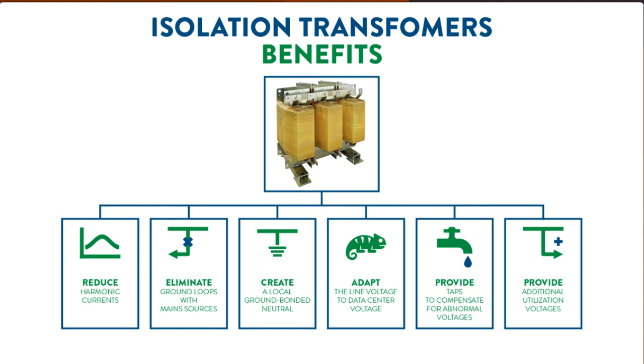But the most important one is to create a local ground-bonded neutral. This allows us to separate the neutral line of the data center or the data center consumers from the mains neutral that comes from the grid. It also allows us to eliminate ground loops from the main sources and reduce harmonic currents, especially the third harmonic and multiples of the third harmonic, such as the 9th, 15th, and so on and so forth.